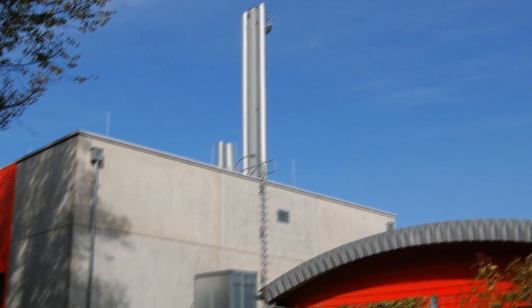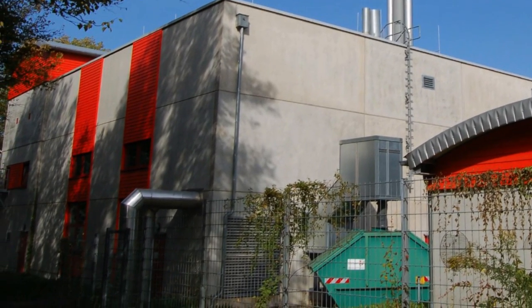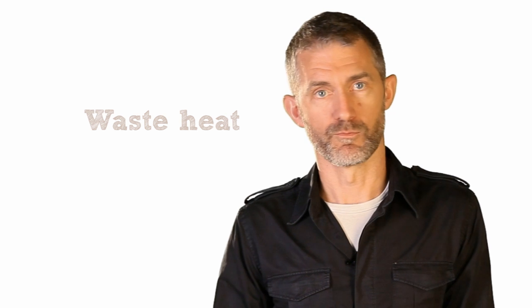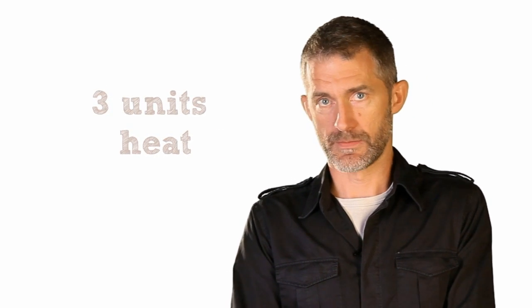At larger scales, typically 1 megawatt and above, a combined heat and power, or CHP, biomass system could be installed. Such a system would typically be designed to burn wood chips to generate electricity. Generating electricity through burning fuel produces waste heat, which is obvious when you look at the cooling towers associated with power stations. Quite often, for every unit of electricity produced, as much as 3 units of heat is also produced. A biomass system that produces electricity, as well as being connected to a district heating network, provides a perfect opportunity to make use of this heat instead of wasting it.